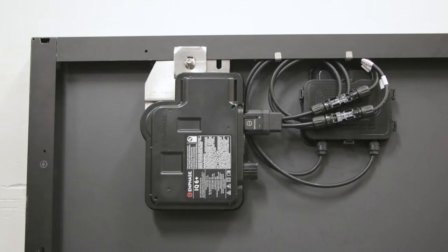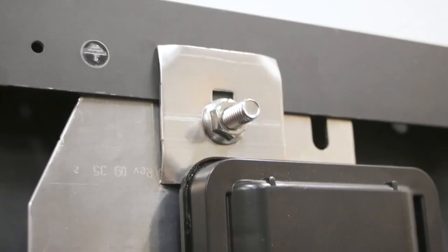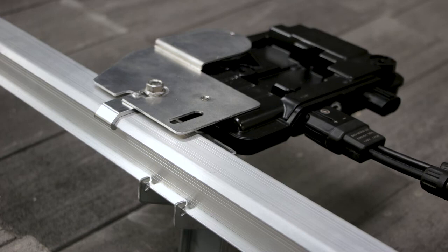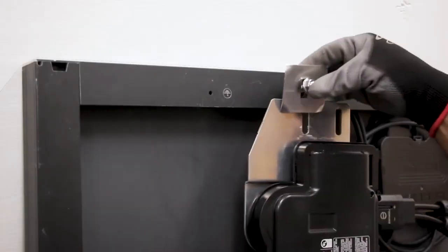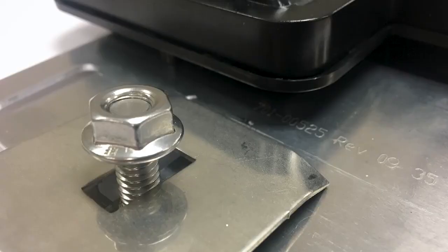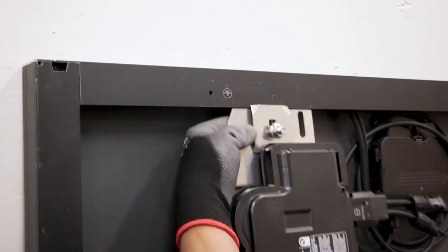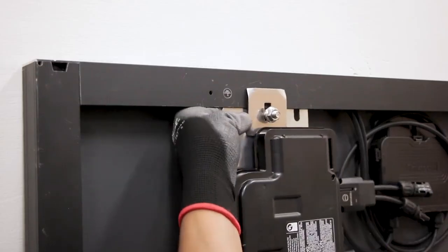Module level electronics can be attached to the module frame using EcoFasten's MLPE clip accessory or directly to the rail using the MLPE bracket. The clip is designed to be threaded onto the inverter or optimizer flange, with the bent corners of the clip pointing down onto the top of the flange. Slide the inverter or optimizer flange underneath the inside of the module frame. The clip slides over the outside of the module frame.